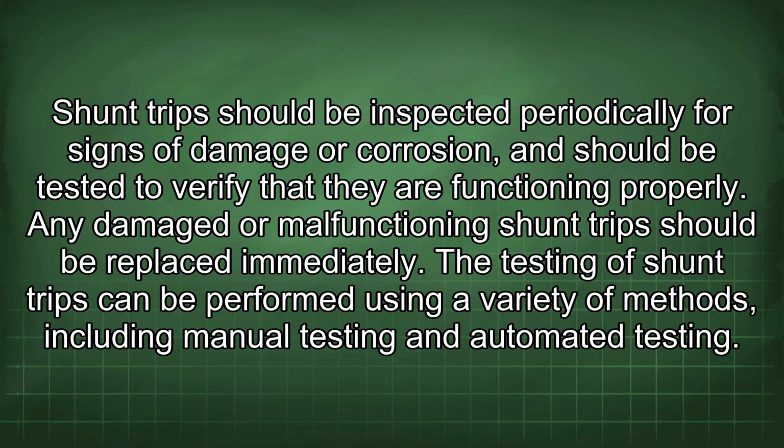Shunt trips should be inspected periodically for signs of damage or corrosion, and should be tested to verify that they are functioning properly. Any damaged or malfunctioning shunt trip should be replaced immediately. The testing of shunt trips can be performed using a variety of methods, including manual testing and automated testing.